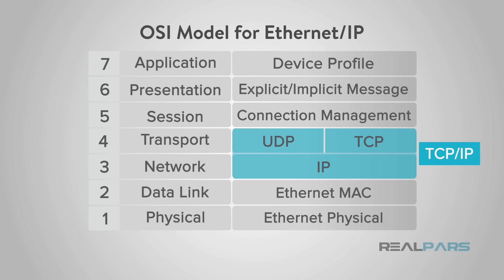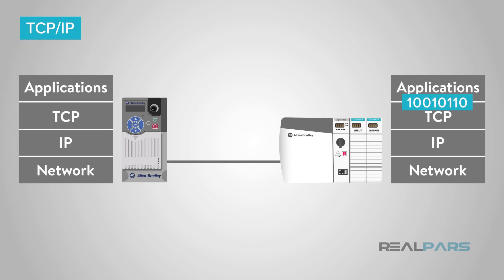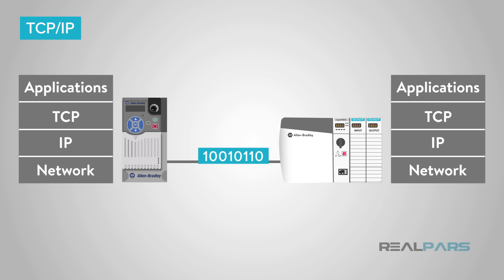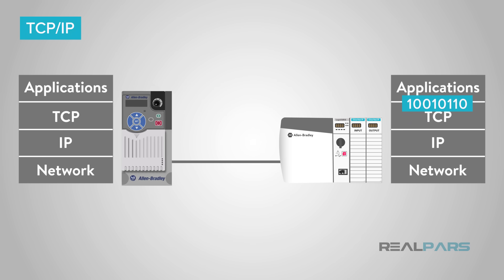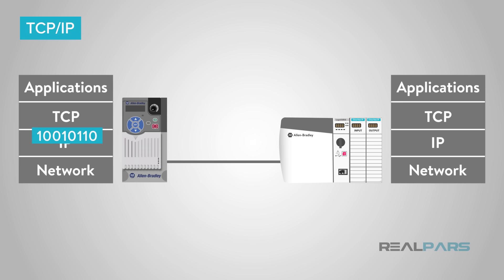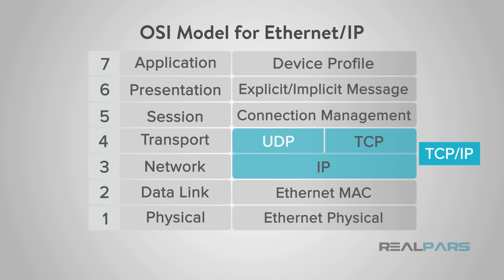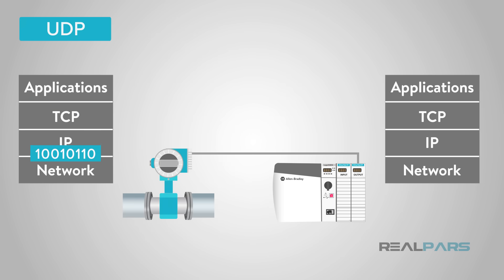We need to break down the TCP/IP or UDP protocols slightly to give you an idea of which application may use which type. In the TCP/IP protocol, there is somewhat of a send-receive-acknowledge relationship. The packets go down the stack, received at the device connected to your network, and a receipt confirmation goes back up the stack to the Applications layer. This type of protocol may be used with a VFD where you command a speed and need to ensure that the VFD received the message. Conversely, with the UDP protocol, this is the continuous transmission, not requiring a receipt acknowledgement.